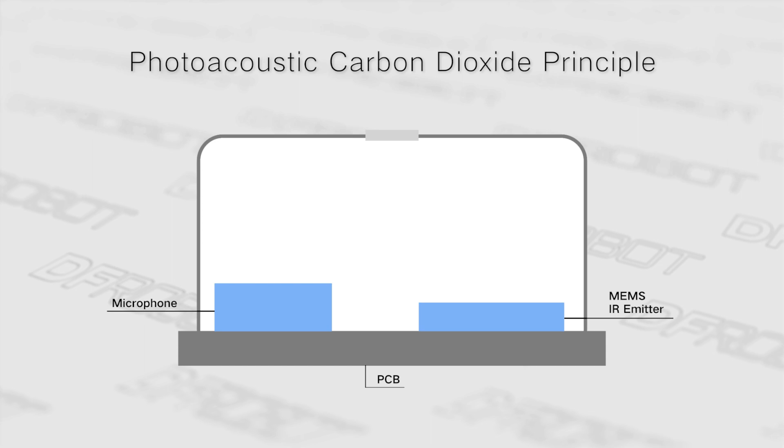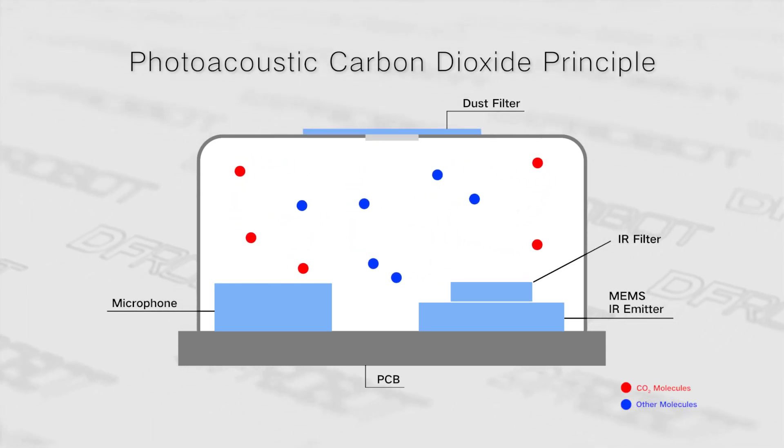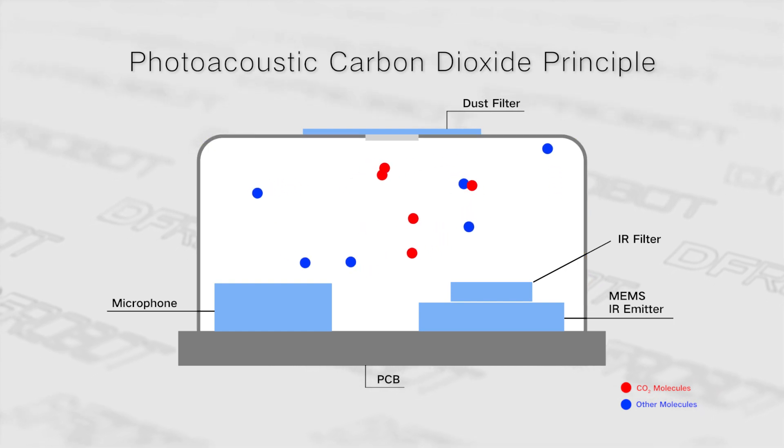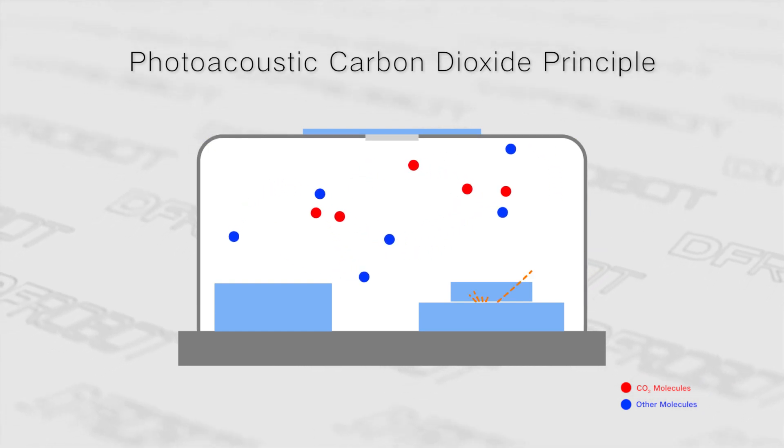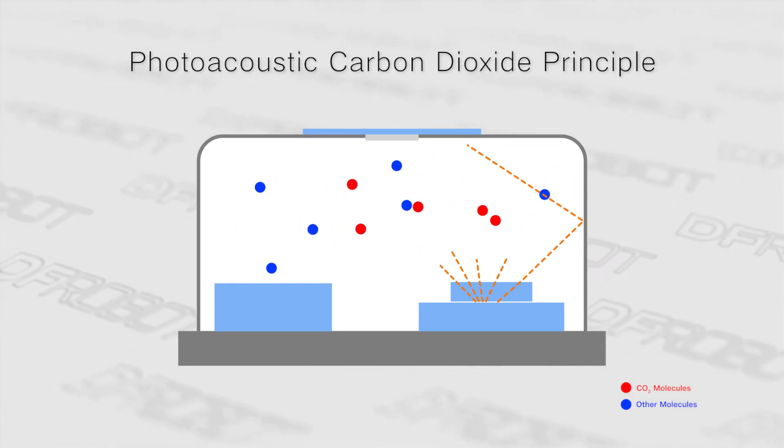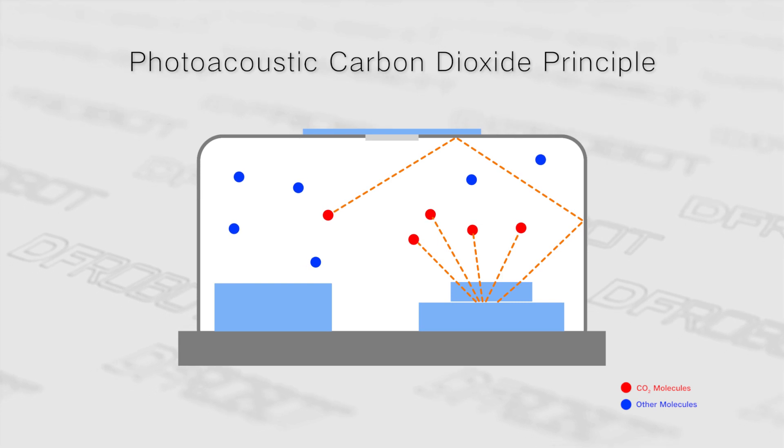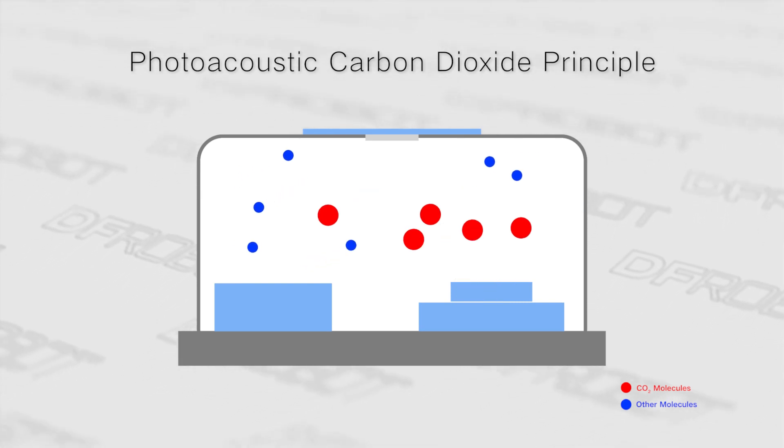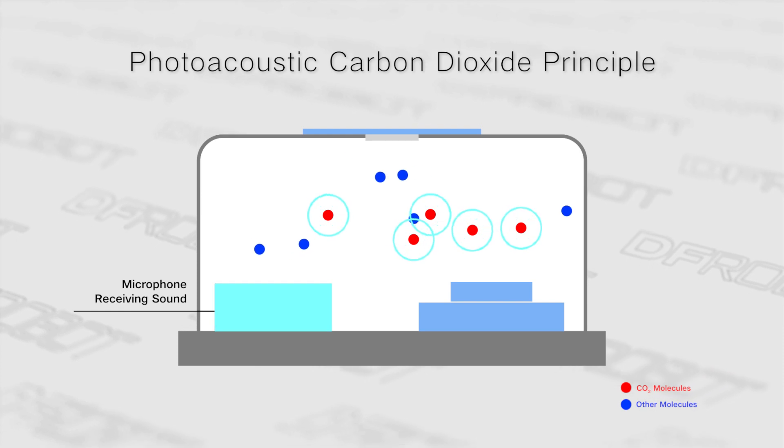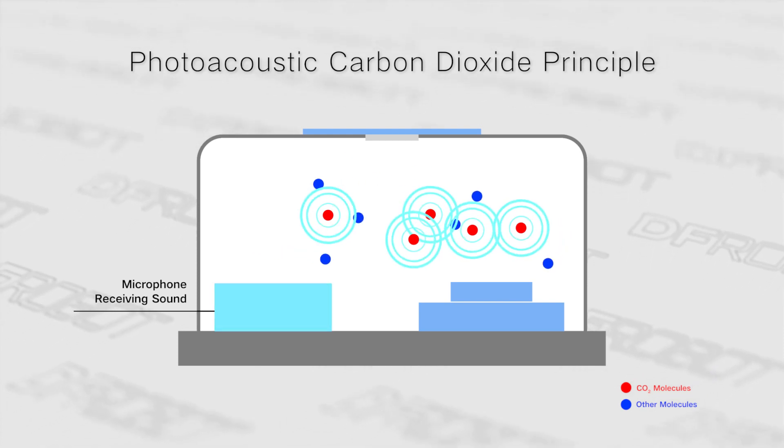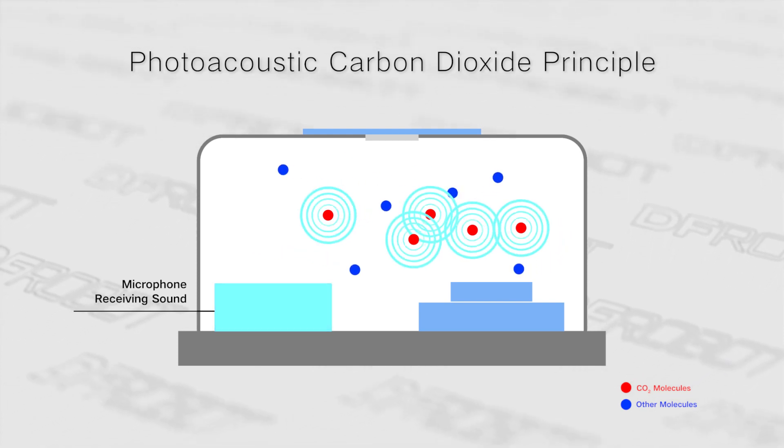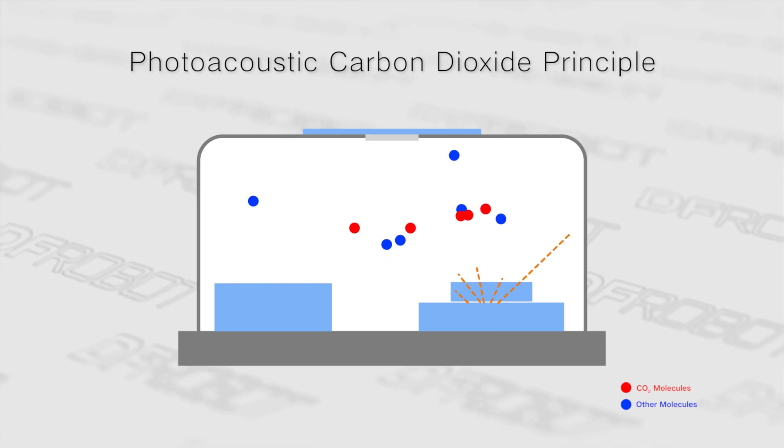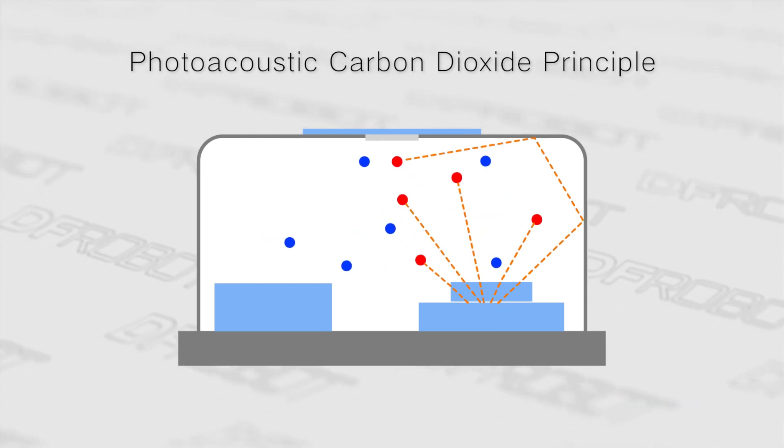In a specially designed chamber, an infrared light source rapidly emits a range of infrared light that passes through a 4.2 micrometer wavelength narrowband filter and delivers energy to the gas. The CO2 molecules in the measuring cell absorb specific wavelengths of infrared light, which causes the gas sample to rapidly heat up and cool down.